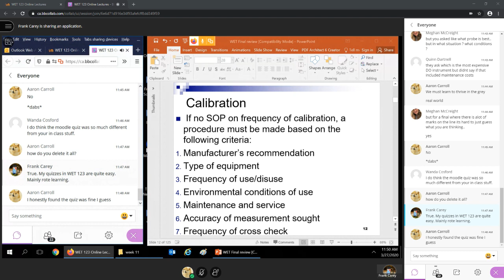And quite often you have to include a deviation chart just to show that the instrument is okay. So if there is no standard operating procedure, each one of these must be factored in when deciding how often to calibrate. I'll let you guys read this, but know where to find this information. What is required? Obviously, a standard. You have to have controlled conditions. You have to have somebody who's trained, and always the chain of custody, the documentation that proves that proper calibrations have always been done with this instrument. So we already know calibration is the key requirement in ensuring control accuracy.